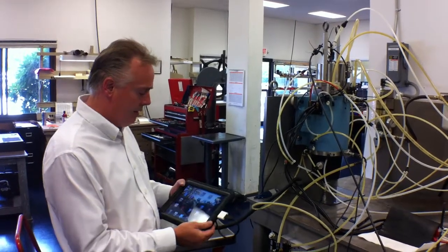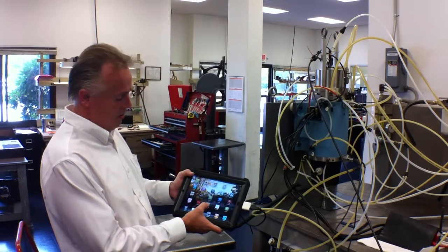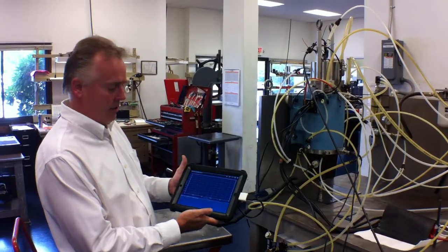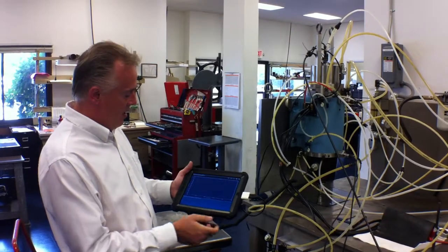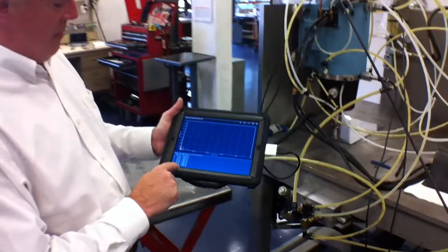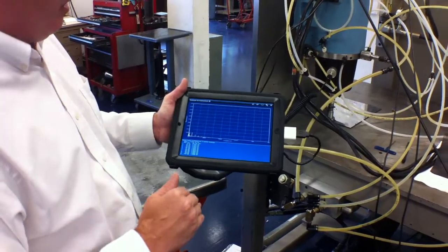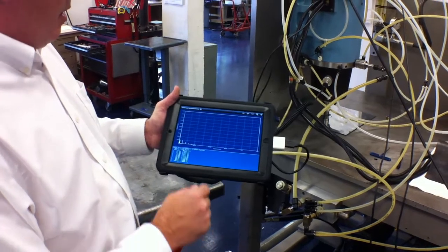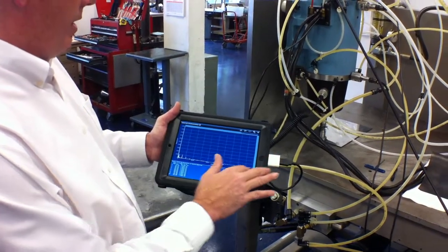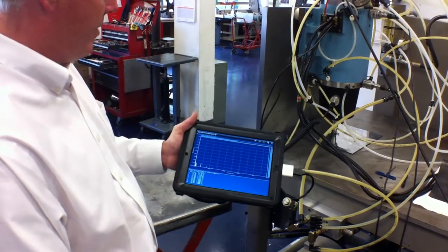We've also refined the application as well. The software signal scope has come up with what we call spindle scope. And as you can see here, open the app. Looks a little bit different than the last one. Gives us full frequencies on the bottom, a list of the top 10 by their highest amplitude down. Also gives us overalls. Obviously not getting much of a reading here because the spindle is just running the air through it right now, but you can see we do get some measure of vibration spectra there.